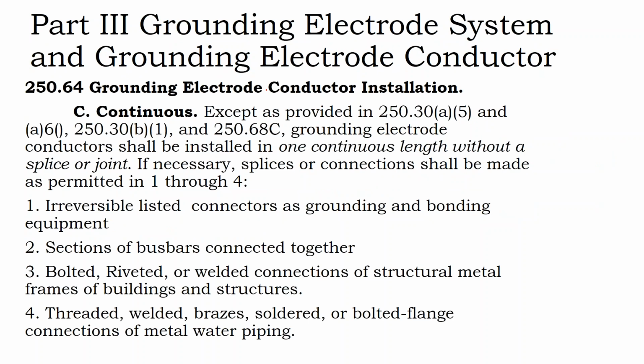So the main thing about this grounding electrode conductor, so remember this is the last stop between the grounding system and the ground rod, is that it needs to be continuous. So does your equipment ground conductor need to be continuous? You know, that green wire in your outlets, what's the shape of it, like a domed square? Does your ground need to be continuous throughout your system? No. You take a metal conduit and a lock nut and you land on a metal box, and then on the other side you have a listed for grounding lock nut and fitting with the rest of your metal conduit. Those are all splices or taps, for a lack of a better word, where you have non-continuous equipment grounding occurring.